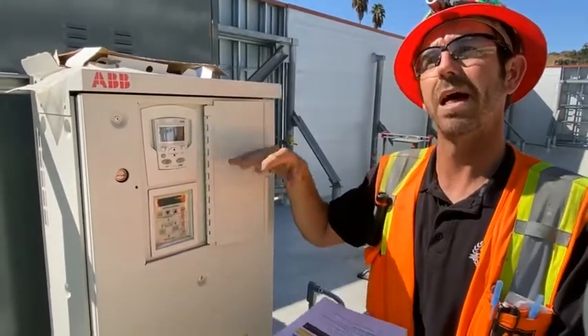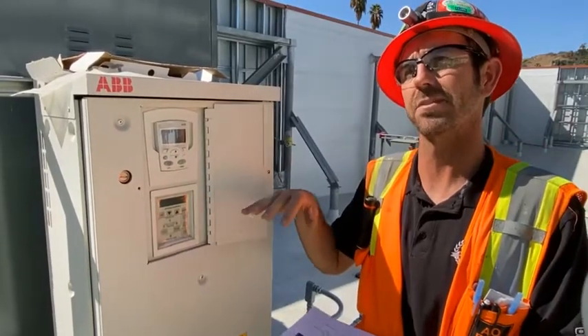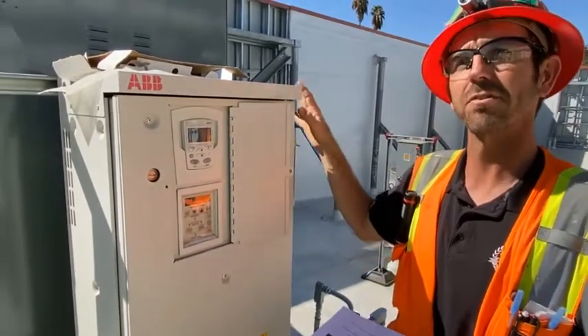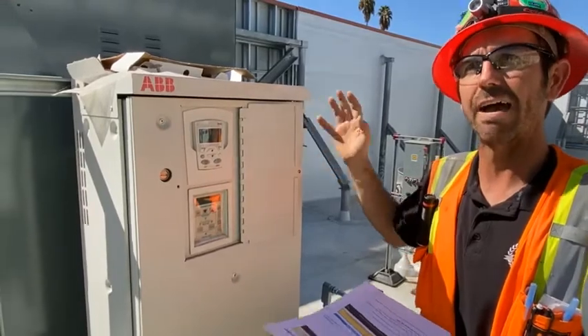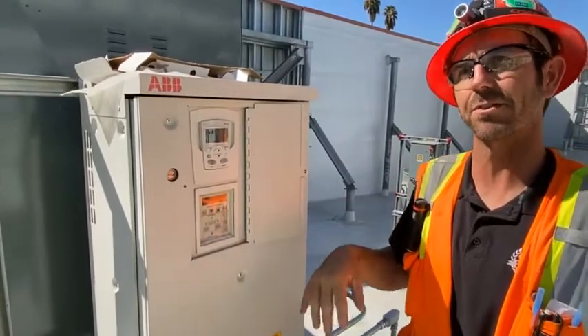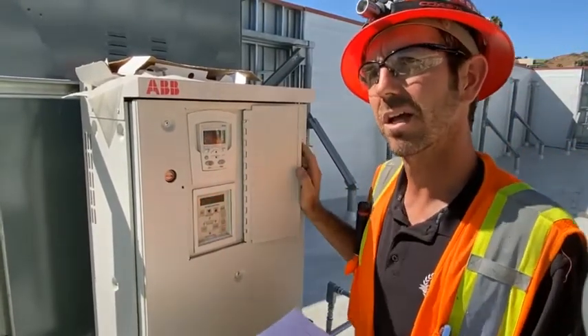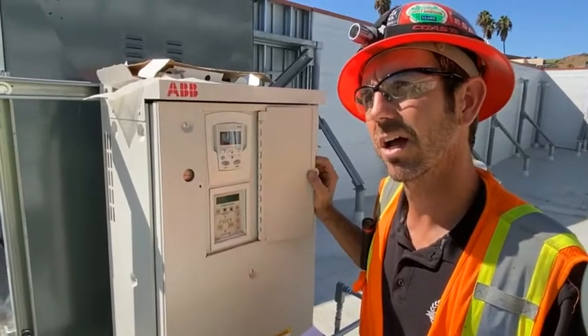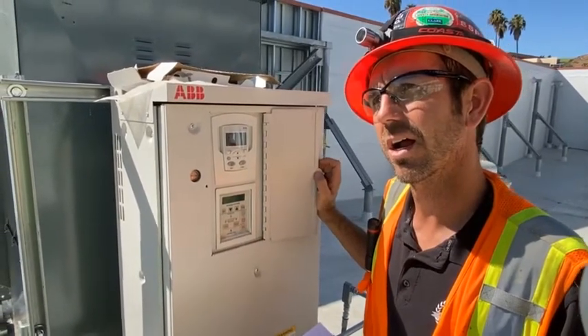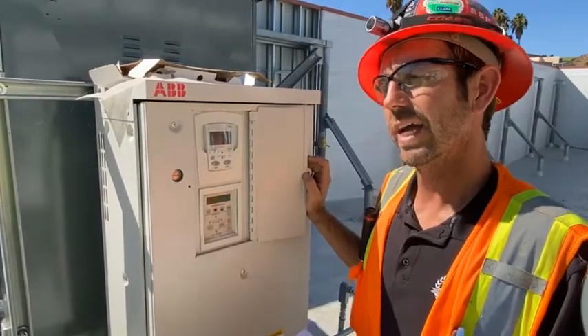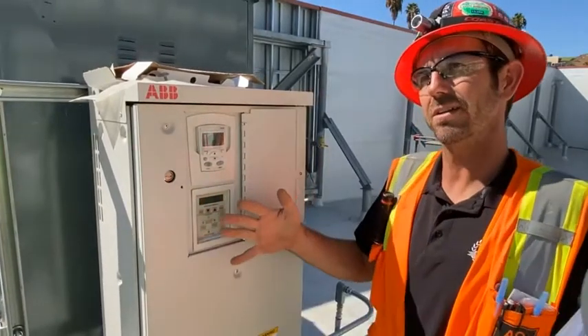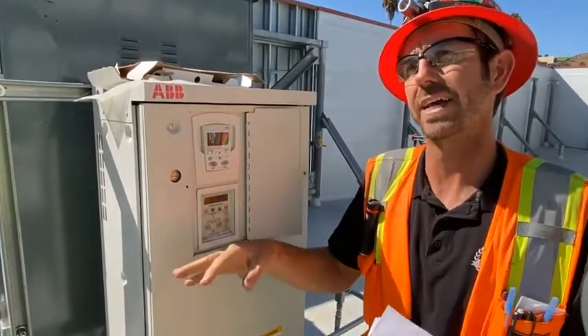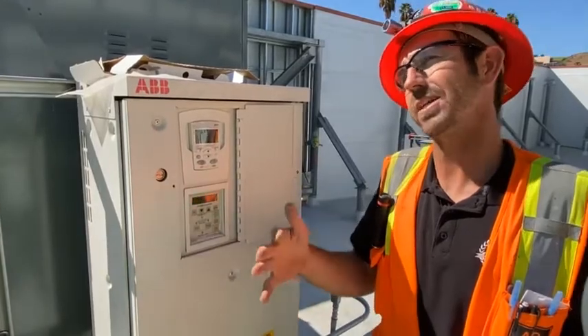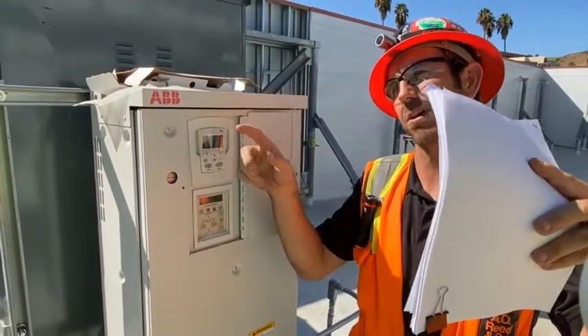This fan's been balanced downstairs to give us the proper CFM. The fan is oversized, so we don't need to run it to 60 hertz. At 43 hertz, we get proper CFM down through the hoods. If our CFMs aren't required downstairs, it'll modulate to compensate, right? It's a constant volume hood, so there's no changing devices down there. The only way it can change is if the grease traps start building up with grease.